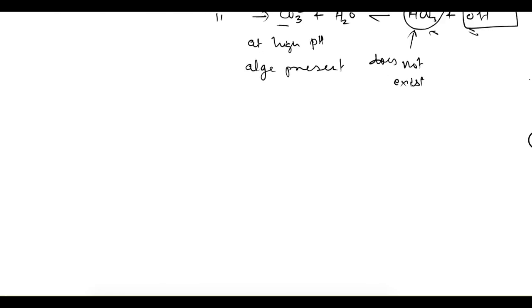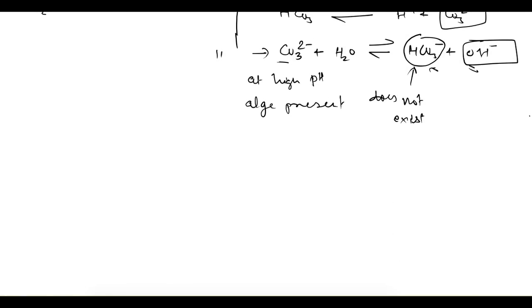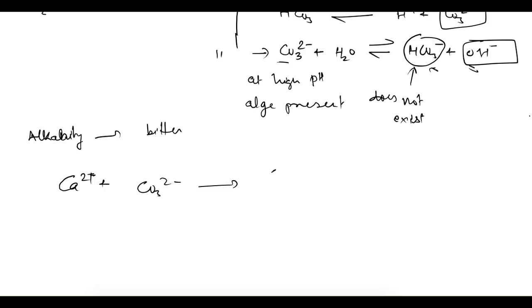If alkalinity is present in water, the taste becomes bitter, so a large amount of alkalinity should not be there. Additionally, if carbonate ions are present, they are free to react with calcium ions, producing a precipitate of calcium carbonate. Because of this precipitate, encrustation of pipes occurs, which is why it should be avoided.